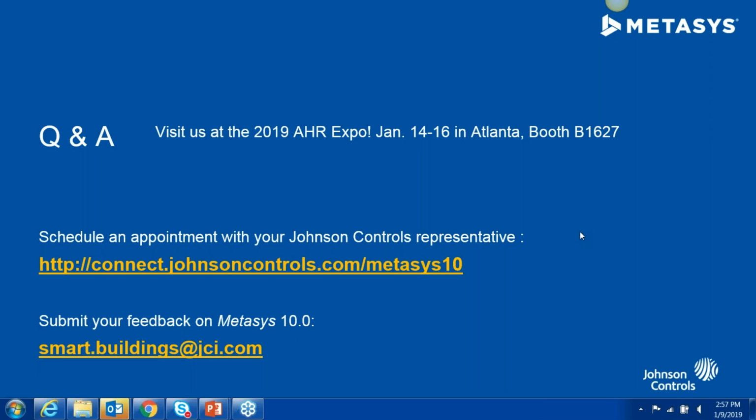Great, thanks. The wireless question. Our equipment controllers aren't, by their nature, wireless. They can be wireless enabled using add-on Zigbee wireless modules that enable them to talk to their peers and to wireless sensors wirelessly, and also up to the network engines using a wireless network coordinator. So by their very nature, the controllers do not talk wireless, but they can be wirelessly enabled using our wireless Zigbee field bus system with add-on wireless modules. Not sure if that answers the question, but hopefully it does.